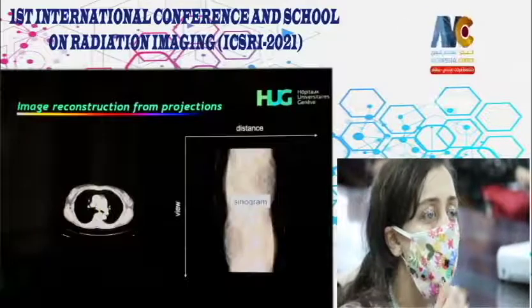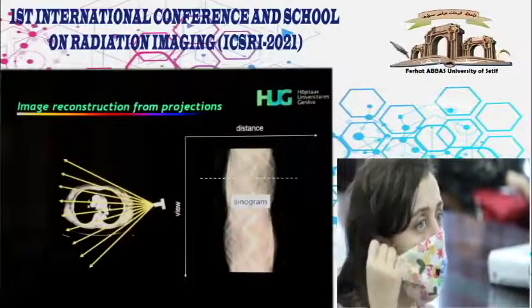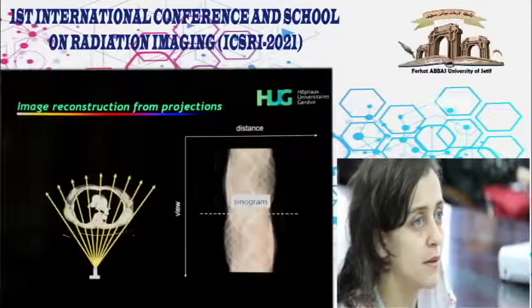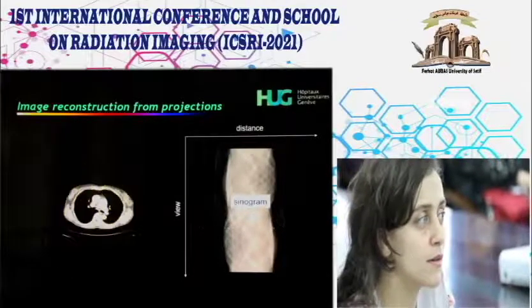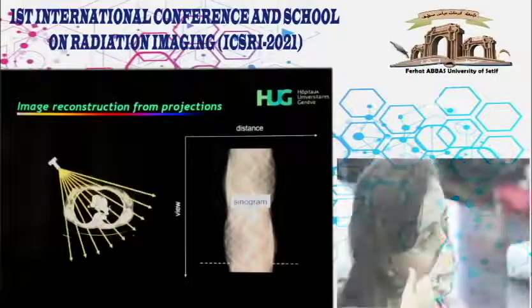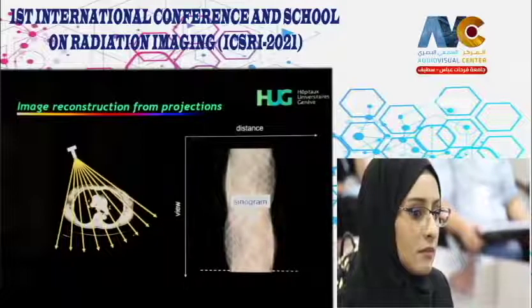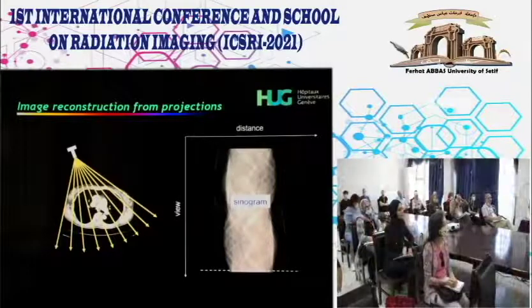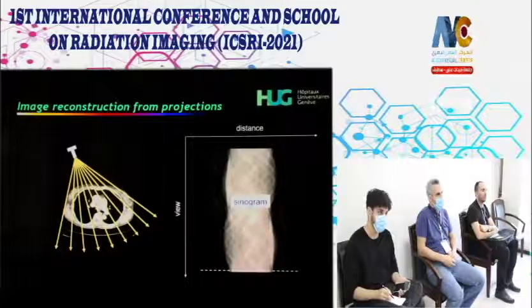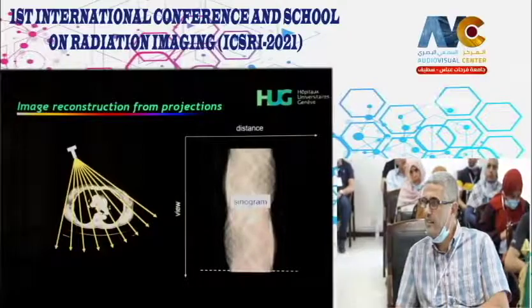Data is collected while rotating the system around the patient in a spiral trajectory. Each line of response corresponds to one point on the sinogram—how we store data on disk. You rotate and collect a certain number of views; each sinogram point reflects a single view angle and a beam distance from the center of the scanner. This applies to both x-ray transmission and emission data.